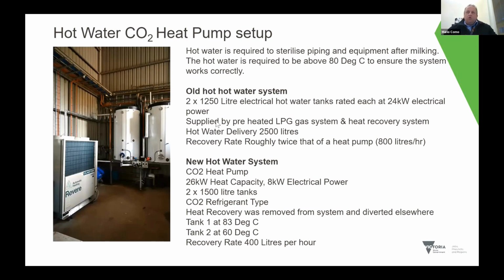Going through the old hot water system: it was two 1,250 litre electrical hot water tanks, each rated at 24 kilowatt electrical power. They were also supplied by a preheated LPG gas system and a heat recovery system from the chiller. Hot water delivery was about 2,500 litres, with a recovery rate roughly twice that of the heat pump, about 800 litres per hour.